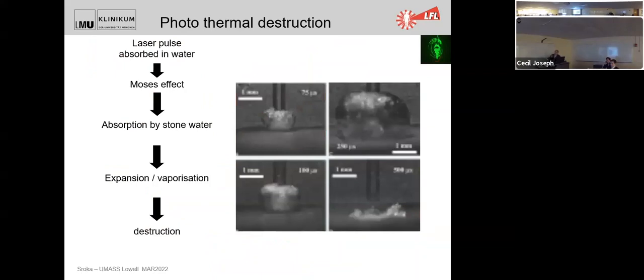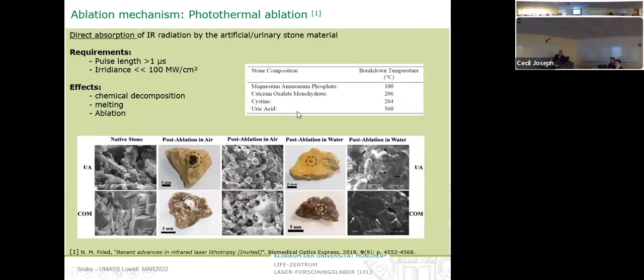And when we think a little bit more in the direction of the infrared laser, the 2 microns, then the laser pulse is completely absorbed in the water, and that's something like a Moses effect. So this is a fiber, here is a bubble, and then the bubble expands a bit, but part of the laser energy can now couple directly into the stone. And then the water in the stone is heated up, vaporized, and then this pressure by vaporization follows the destruction of the stone in a very, very small manner. But for this effect, we need longer pulses.